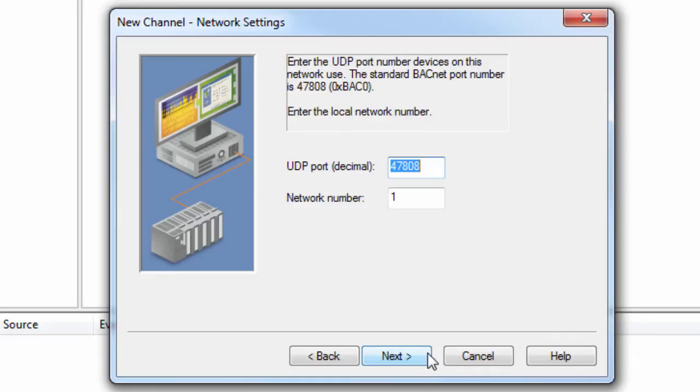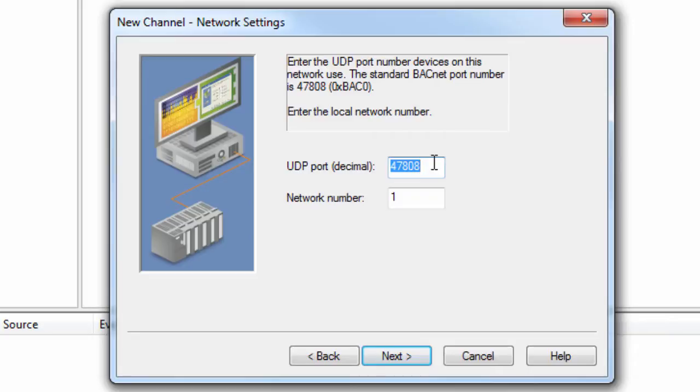Click Next to set the network settings. The UDP port can be left at default unless your device is using a port number other than the recommended port for the BACnet protocol. Typically, all BACnet IP devices on an Ethernet network use the same port. Since this is an Ethernet driver, configuring a unique channel per device can increase the driver's performance.